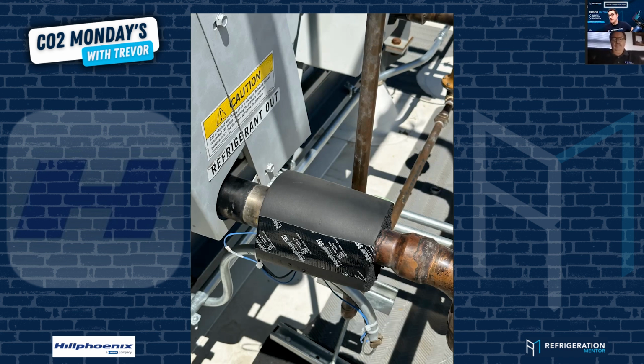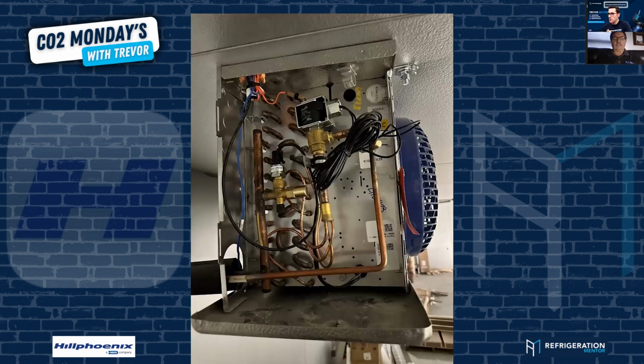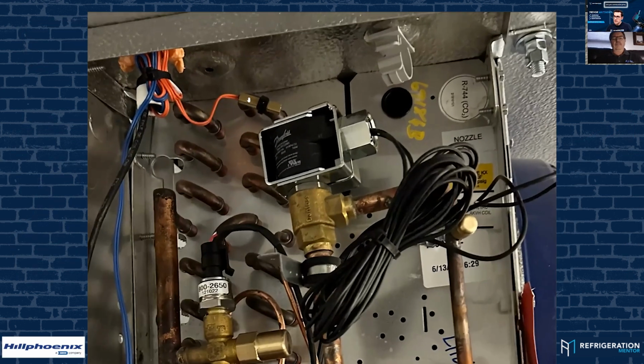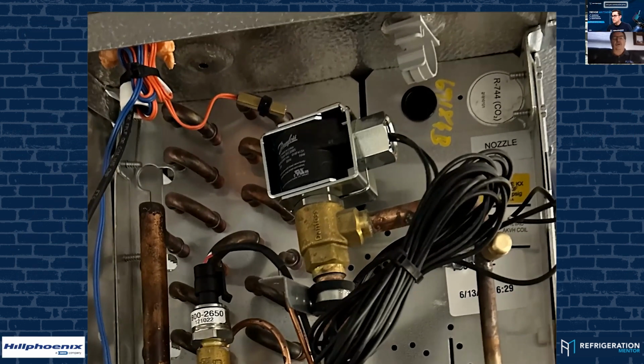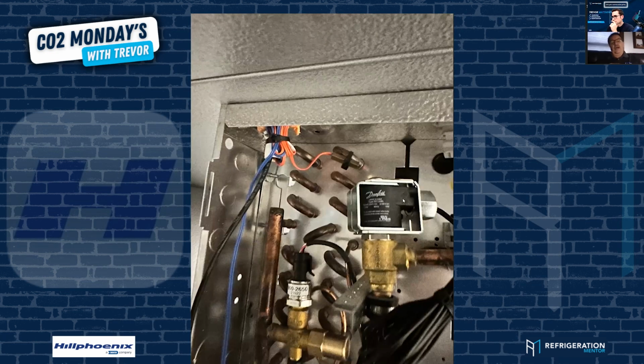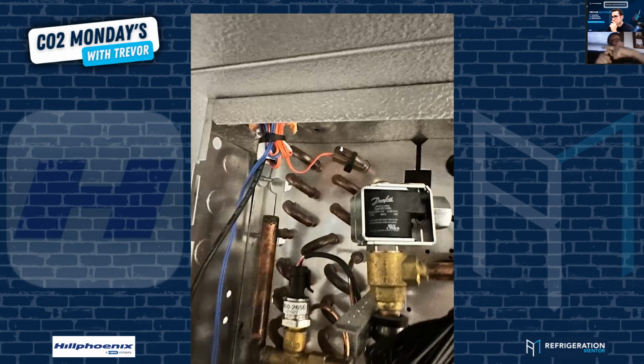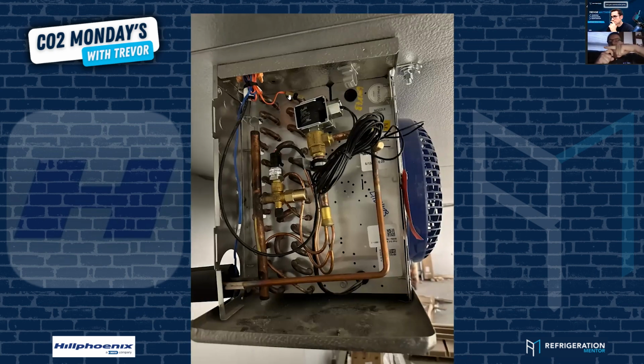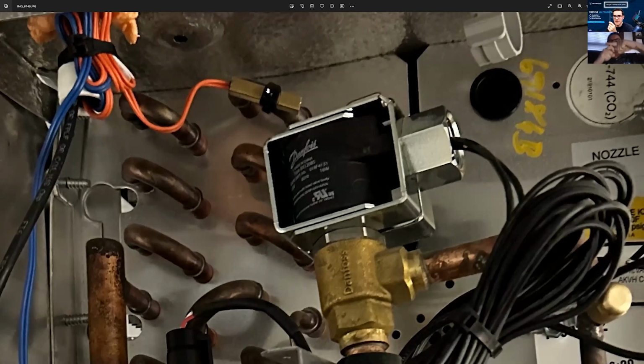So that's why this sensor is so important. I think we got two more pictures here. So one here, and we're talking about this one here. So this is the termination sensor on the Heatcraft evaporators. That sensor's square and it's on the end of the return tube. So how much contact do we have? About that much, just like a touch. Turn it and put it on the side, so at least 2 points are in contact.